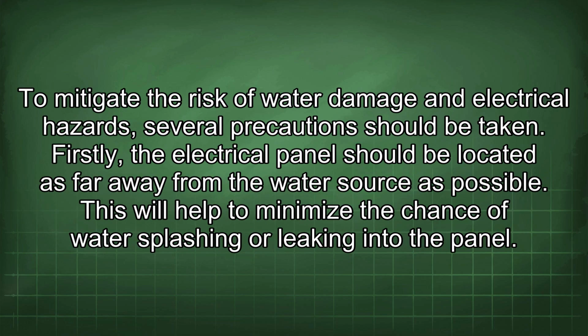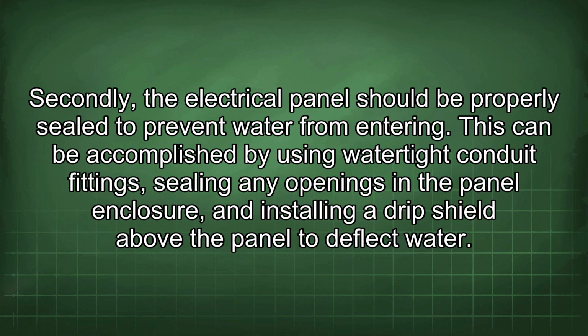To mitigate the risk of water damage and electrical hazards, several precautions should be taken. Firstly, the electrical panel should be located as far away from the water source as possible to minimize the chance of water splashing or leaking into it. Secondly, the panel should be properly sealed to prevent water from entering, using watertight conduit fittings, sealing any openings in the enclosure, and installing a drip shield above the panel to deflect water.